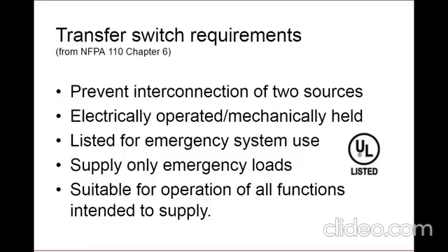So there are many additional transfer switch requirements listed in the codes, especially NFPA 110. So that's kind of a separate seminar all in itself. So here are just a few highlights that you should be aware of in the design and specification of your switches within the EES. First off, mechanical interlocking is required to prevent inadvertent connection of the primary power supply and the emergency power supply. Transfer switches must be electrically operated and mechanically held. They are required to be listed specifically for emergency use, and this listing must be by an independent third party, such as UL. They must supply only emergency loads, which are the loads we just discussed earlier for each branch, and they must be suitable for the operation of all functions they are intended to supply. For instance, if it's going to feed inductive loads or nonlinear loads, it must be designed and suitable for that use, such as the switch capacity or interrupting rating.